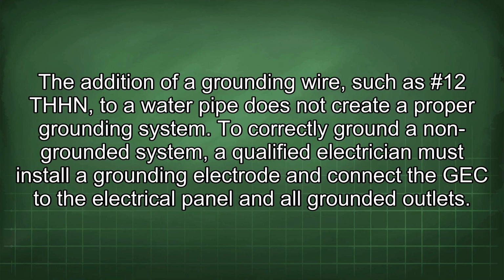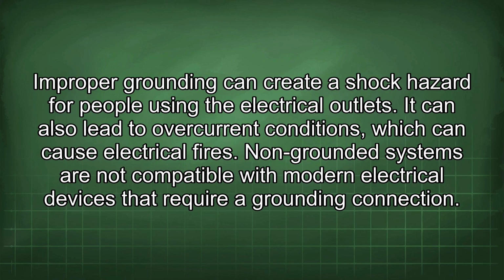The addition of a grounding wire, such as #12 THHN, to a water pipe does not create a proper grounding system. To correctly ground the non-grounded system, a qualified electrician must install a grounding electrode and connect the GEC to the electrical panel and all grounded outlets. Improper grounding can create a shock hazard for people using the electrical outlets. It can also lead to overcurrent conditions which can cause electrical fires.